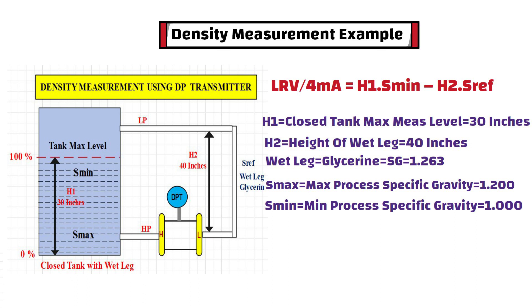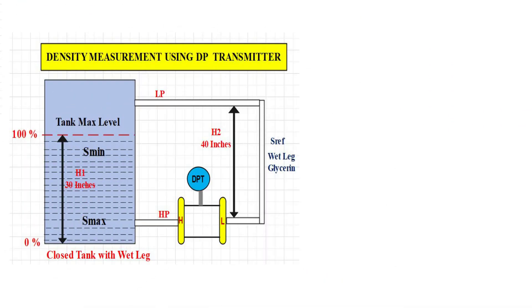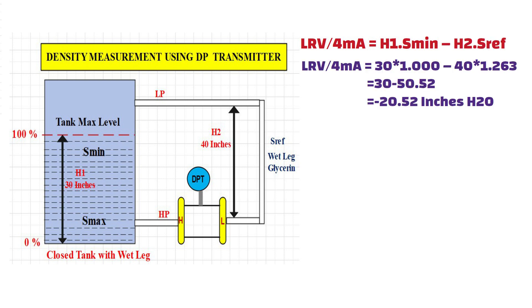Now, let's put all these values into the equation and do the simple math calculation. As you can see, when we put all these values into the equation, we get minus 20.52 inches H2O, which is our lower range value for this DP transmitter in this example.